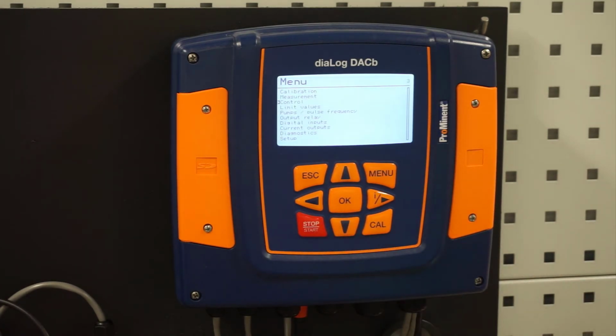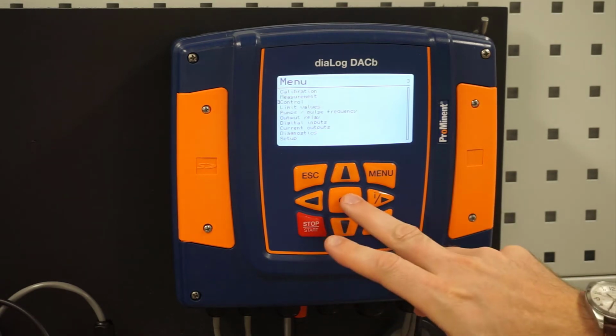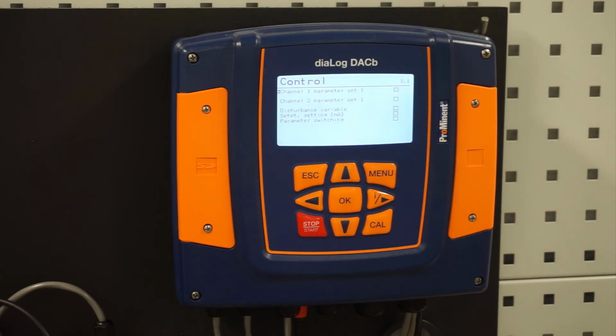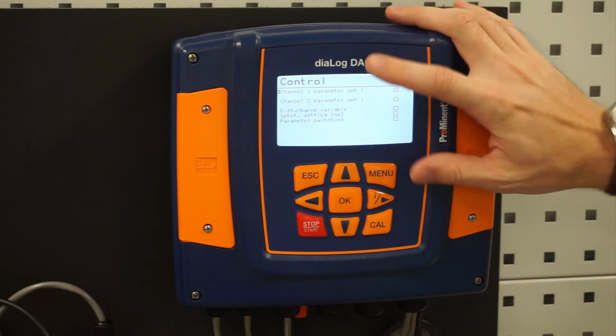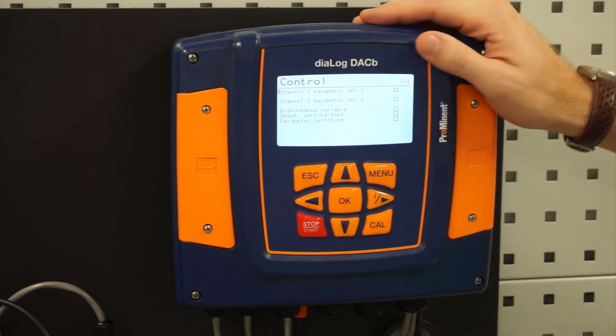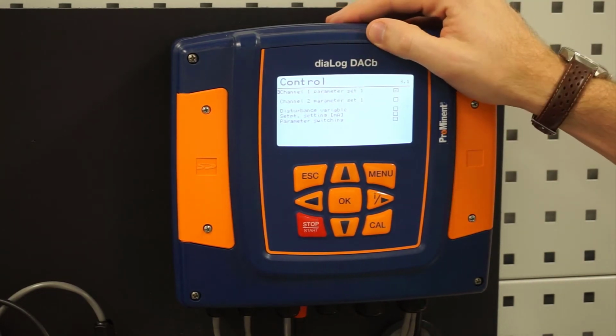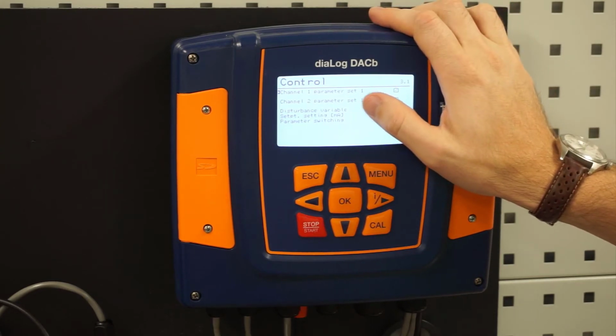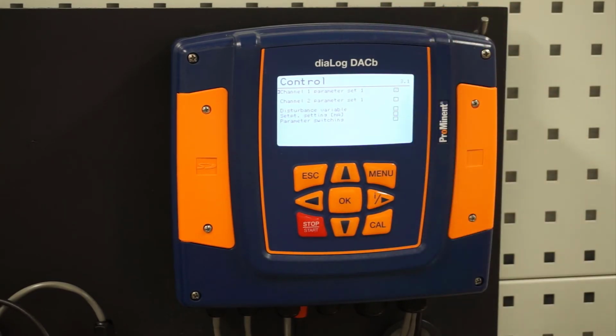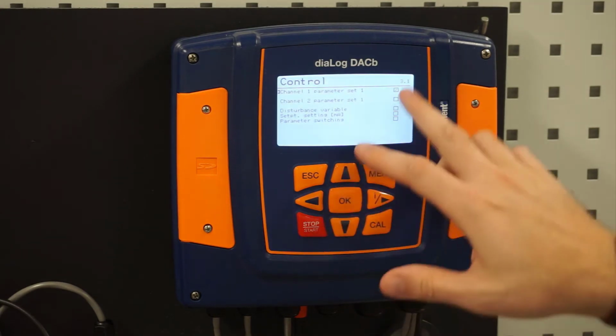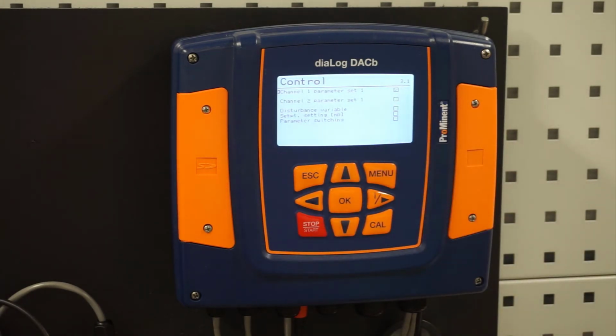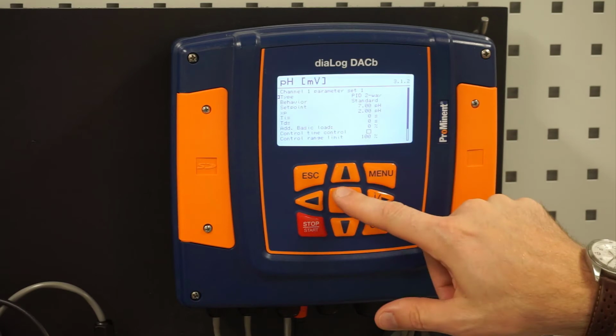If we are controlling locally from here, if we have our universal control cable in there going to a gamma L or gamma X pump, for instance, we would need to set up our control screen. So I'll give you an idea of what's in there. First thing we would do in there is we would need to figure out, all right, which channel do we want to control with? In this case, pH is on channel 1, so we'll set that up to control maybe an acid pump. You can see there's a check mark next to it, so it's already set up to do something. So if I hit OK, the first thing it's going to say is what type of control do you want?